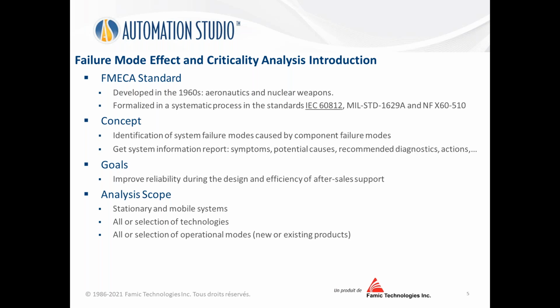The scope of the analysis finally is that the FMECA is applicable on both stationary and mobile systems. It can be applied on the entire system, or part of the system. You can apply this only on a specific technology, let's say hydraulic, electrical, or pneumatic, but you can apply it on all. As well, you can select all the operational modes of all the functions, but you can also apply FMECA only on a new function or new options that are developed on an existing product. So it is really open. You can apply FMECA on a new project, but also on an existing project.